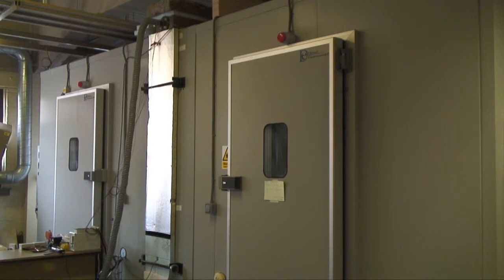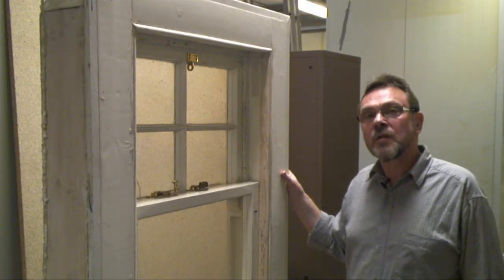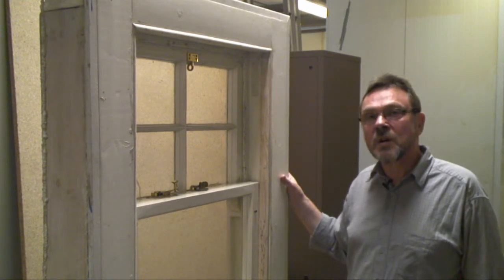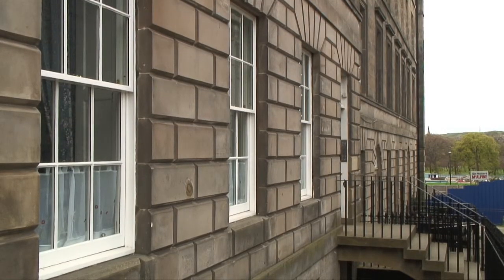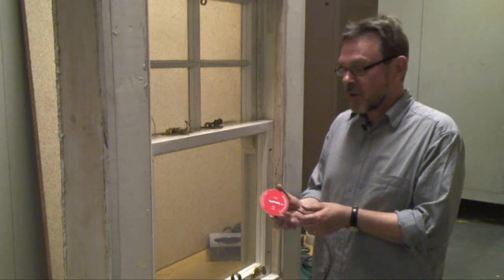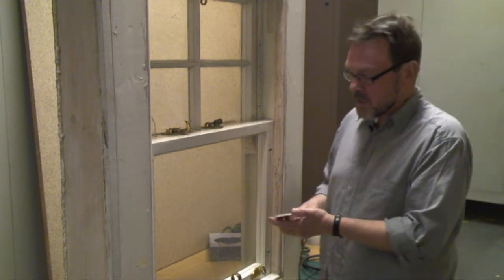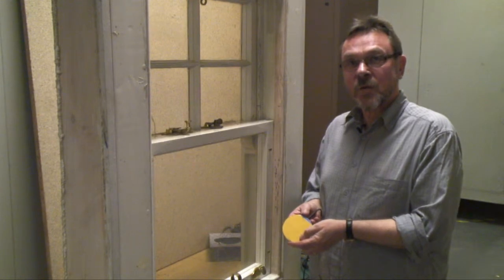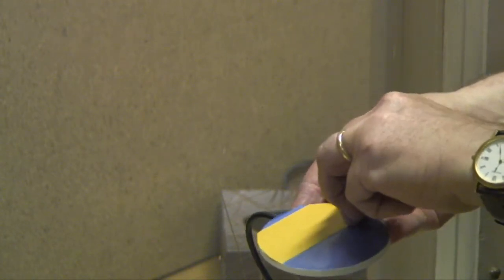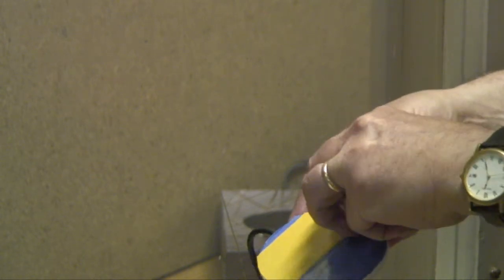This is a typical example of the type of window that we have been testing, both for Historic Scotland in the lab, and also carrying out in situ measurements for Changeworks at Lauriston Place in Edinburgh. This is the type of heat flux sensor that we use typically for these kinds of tests, both in the lab and in situ, both on glazing and on wall constructions. For windows, we back the sensor with double-sided tape, thoroughly clean the surface of the glass, and then stick the sensor onto the window, usually in the middle of the pane.